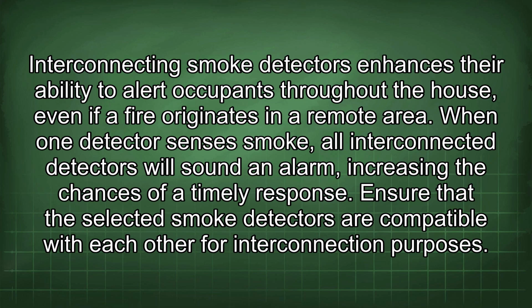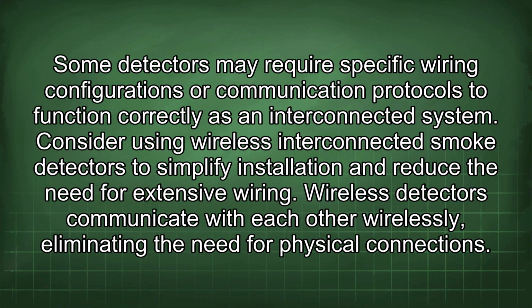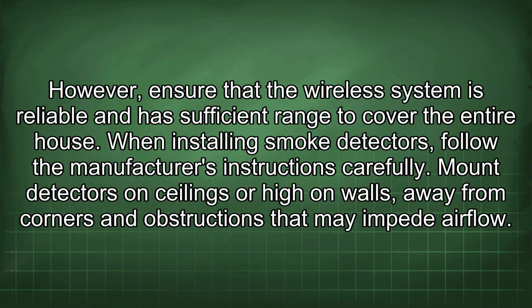Ensure that the selected smoke detectors are compatible with each other for interconnection purposes. Some detectors may require specific wiring configurations or communication protocols to function correctly as an interconnected system. Consider using wireless interconnected smoke detectors to simplify installation and reduce the need for extensive wiring. Wireless detectors communicate with each other wirelessly, eliminating the need for physical connections. However, ensure that the wireless system is reliable and has sufficient range to cover the entire house.